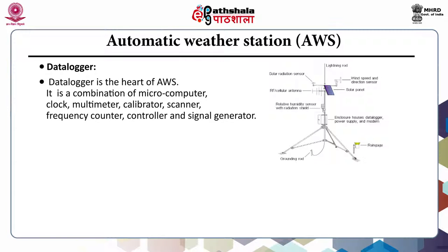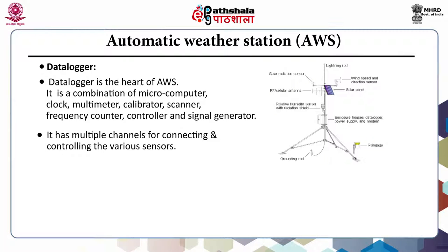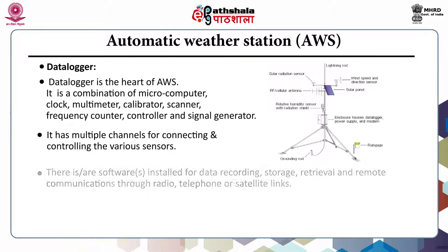The data logger is the heart of the AWS. It is a combination of microcomputer, clock, multimeter, calibrator, scanner, frequency counter, controller and signal generator all in one box. It has multiple channels for connecting and controlling various sensors. Software installed inside the data logger guides the sensors on how to collect data, at what interval, how to store it, how to retrieve the data, and in case of remote communications, how it should be communicated through radio, telephone, or satellite links.